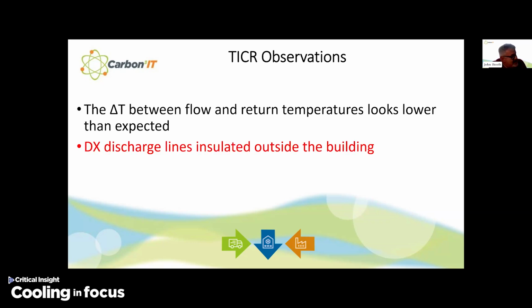We found DX discharge lines insulated outside of the building. And that's another easy win. So if you've got insulated pipework coming from your internal to the external, remove that insulation. It's really not needed. The whole of the cooling plant should be classed as a level 3 secure area. So the only people that should be allowed in it are data center personnel and air conditioning personnel, and they should know how they should operate in that area.